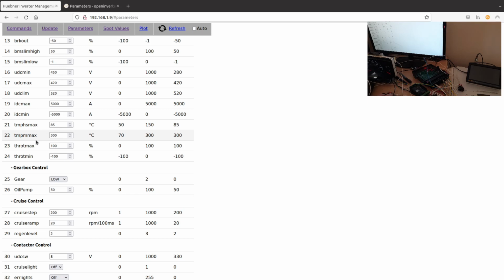TMPHS max and TMPM max. TMPHS max is shorthand for temperature heatsink maximum, the maximum temperature at which we allow 100% driving and regen torque to be commanded. If temperature exceeds that, we start to derate. Likewise, TMPM max is temperature motor maximum, and that has the same effect.